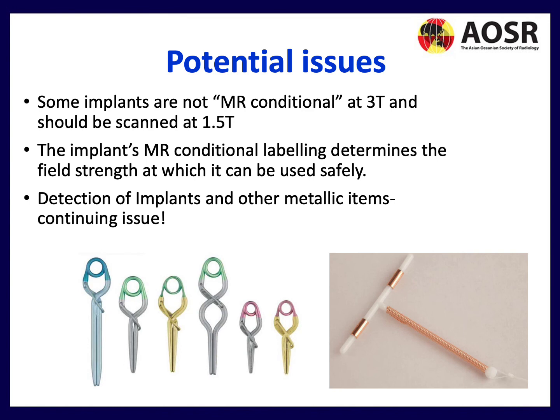Other potential issues are that some implants are not MR conditional at 3T and should be scanned at 1.5 Tesla. The implant's MR conditional labelling determines the field strength at which it can be used safely, so always keep this in the back of your mind.